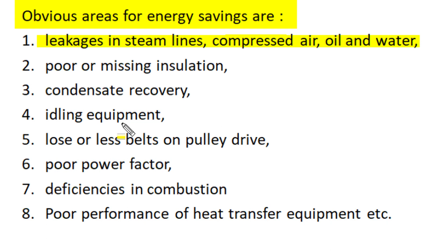In steam lines, condensate creates problems in heat transfer, and condensate recovery can prove a good solution for energy efficiency improvement. Many a times we continuously run equipment in idling conditions without any effective output, and if one stops such idling equipment, one can save a good amount of energy. Many a times when we use belt pulley power transmission in our motors and operating systems, loose or fewer numbers of belts on pulley drives can be identified by such walkthroughs, and improvement in belt tension or number of belts on pulley drives can improve energy efficiency.